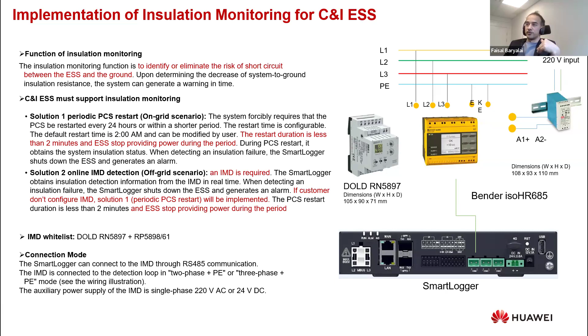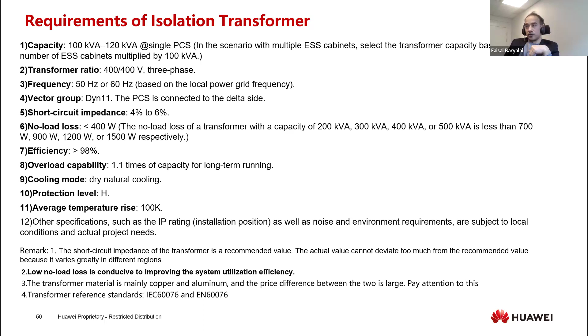So there are some requirements for the isolation transformer, the capacity. We need a 100 kVA transformer for each PCS cabinet. There are several PCS, so several cabinets. We just multiply from 100 kVA up to 120 kVA per cabinet for the total capacity of the isolation transformer. And some other specifications: the transformer ratio should be 400 to 400 volt, 3-phase, and the vector group should be Dyn11. The PCS is connected to the delta side. Then we have some other specifications which could be taken into account when we purchase the isolation transformer.